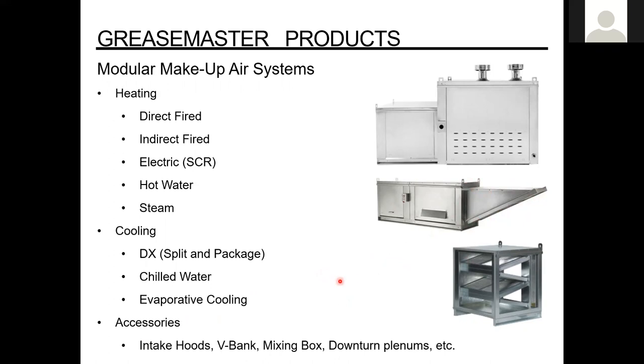Big thing with that is I would always recommend people putting V-banks on them. You're still going to get some particulate coming out through here, but usually if you're using a makeup air plenum, those plenums with the supplies usually get clogged up. So that's a problem I've seen in the past where I've walked into a restaurant and the guy's like, well, the hood system's not working. We're looking around and his exhaust is working properly. His makeup air is kind of overloaded and we couldn't figure it out. Go look at the intake hoods. Oh yeah, everything looks good there. Lo and behold, we look up at the makeup air plenum and it's full of dust and dirt and all kinds of stuff. So you definitely want to be cleaning those plenums out.